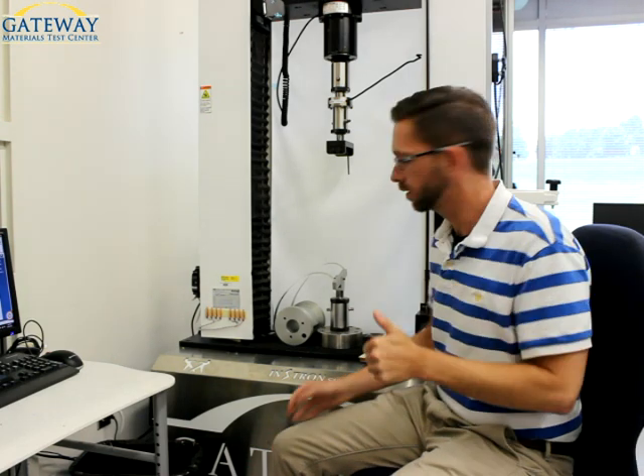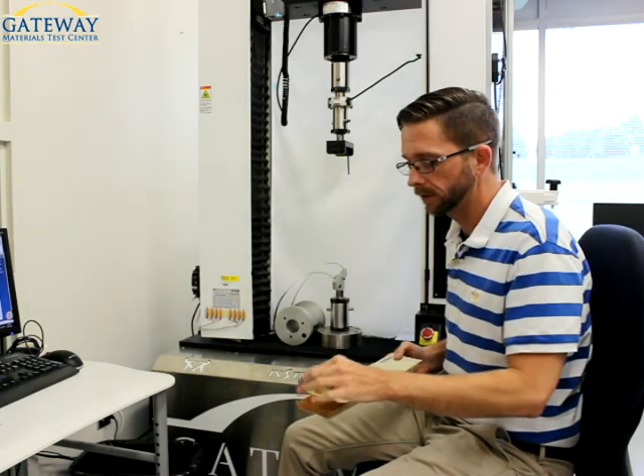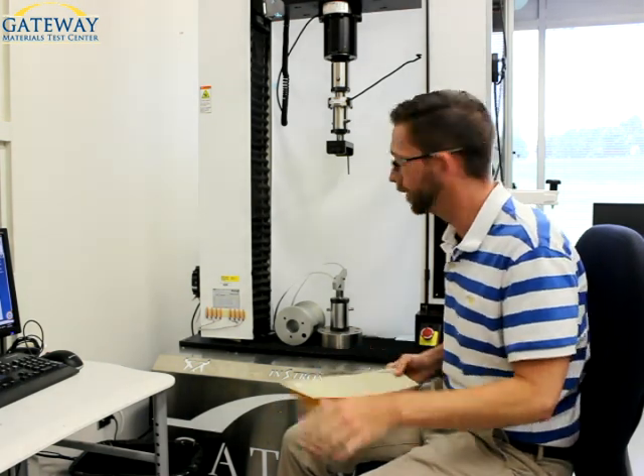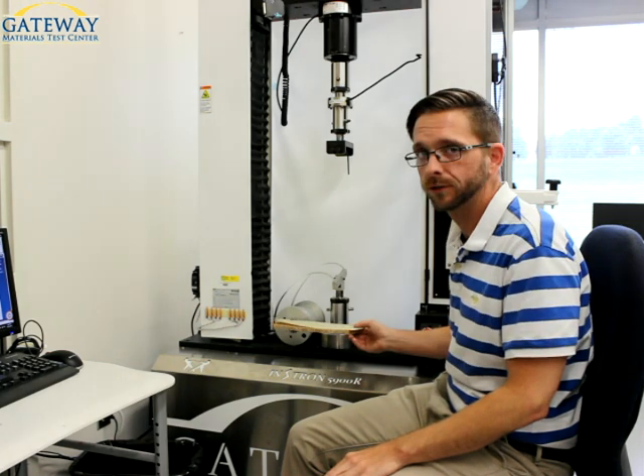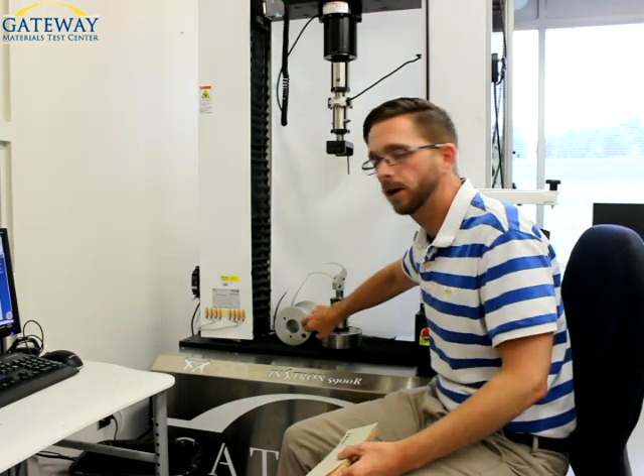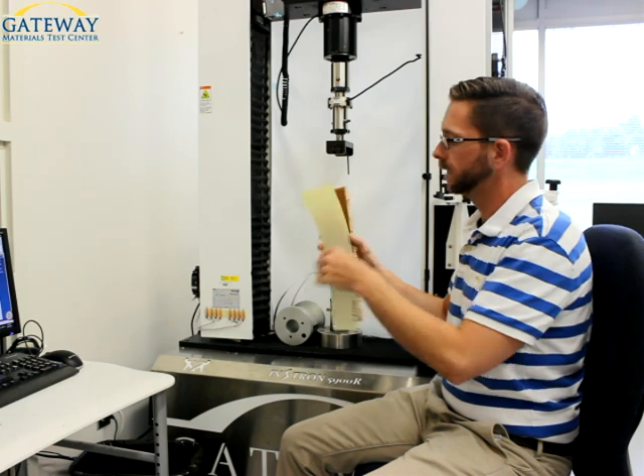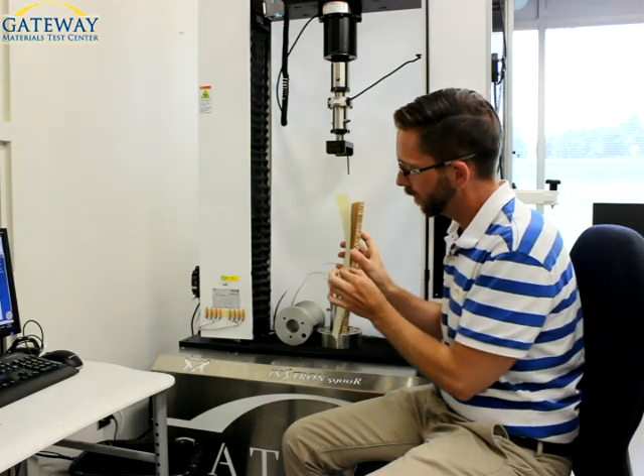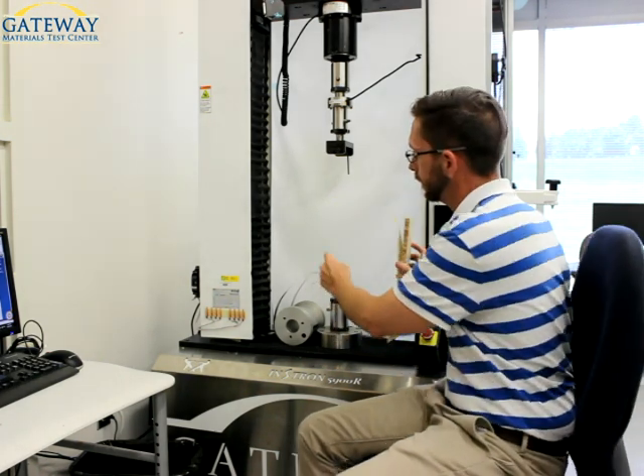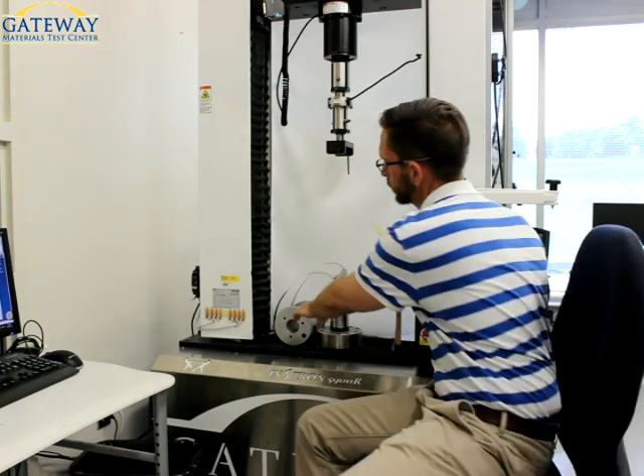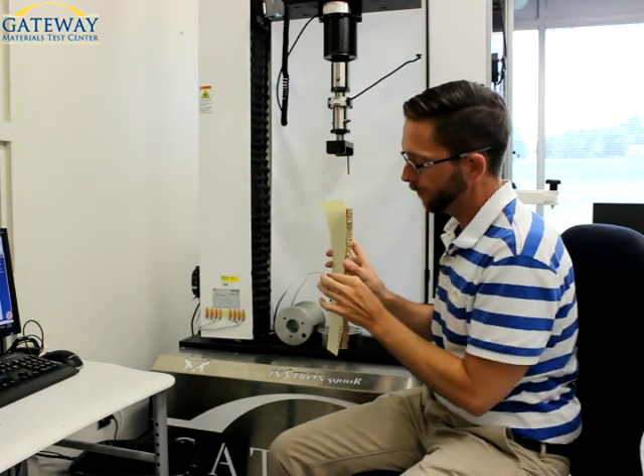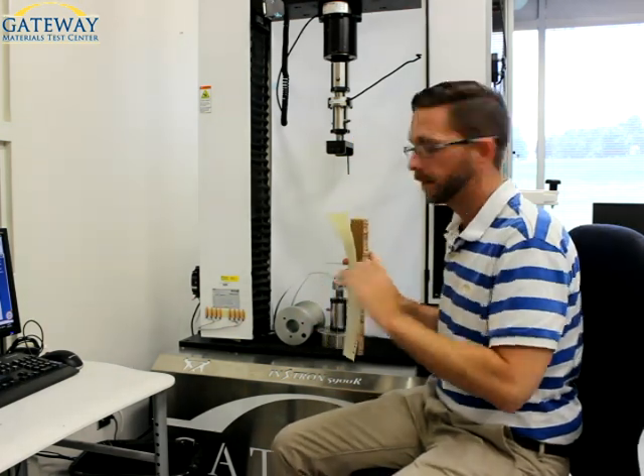So we're looking for an average peel strength, like I was talking about earlier, the force necessary per width to peel this off. But since we have a climbing drum peel fixture here, we're also worried about torque, because there is a nominal distance away from this facing that the drum peel is away from it. So there's a torque necessary in order to calculate.